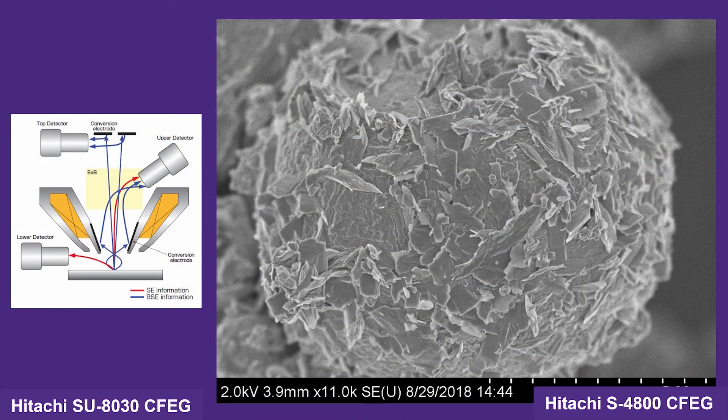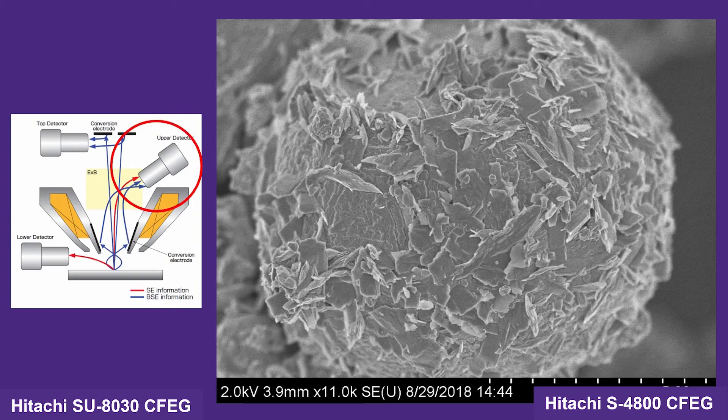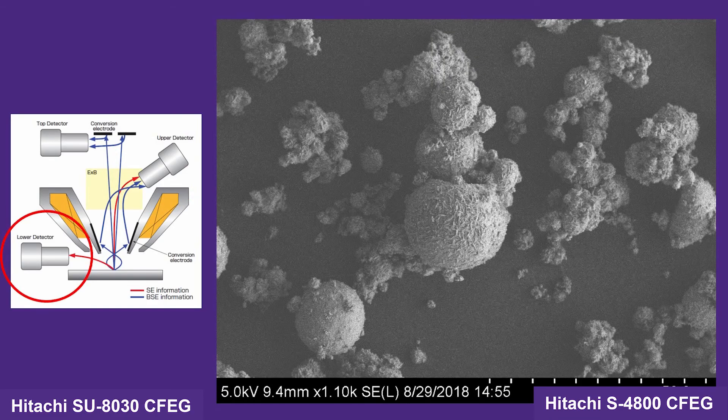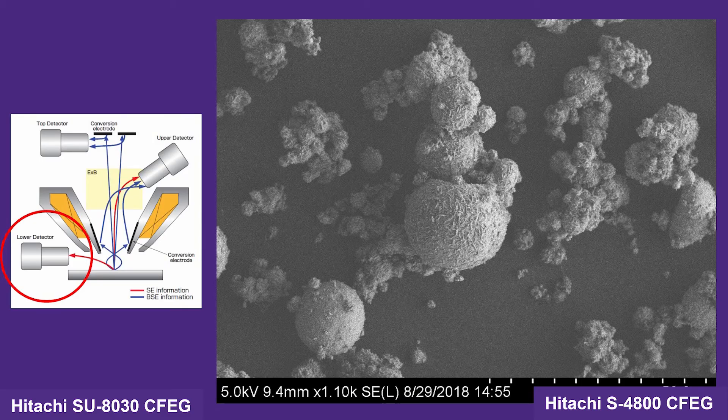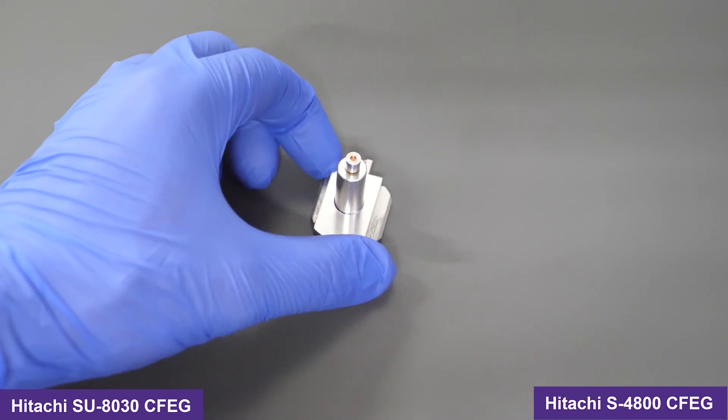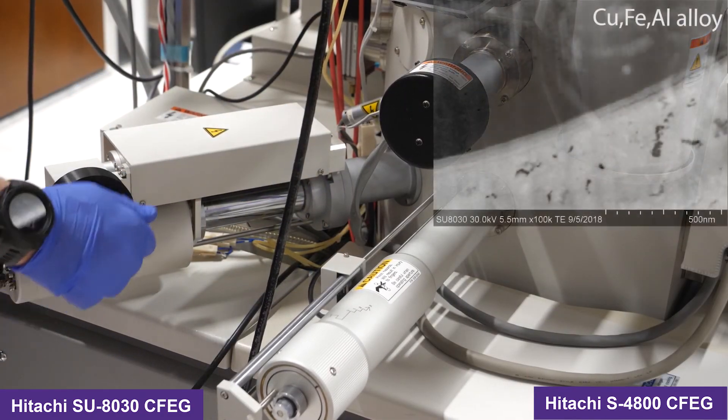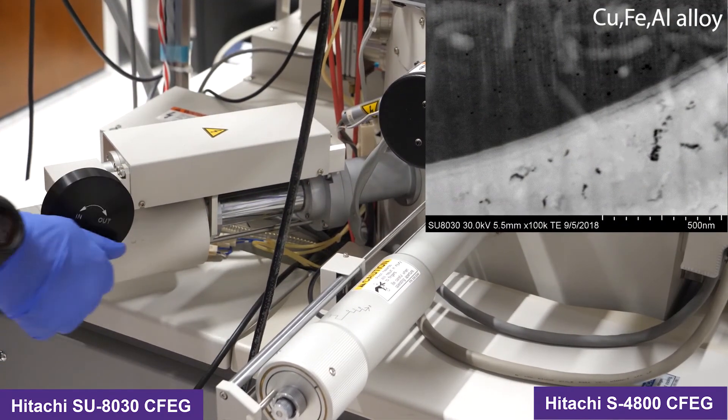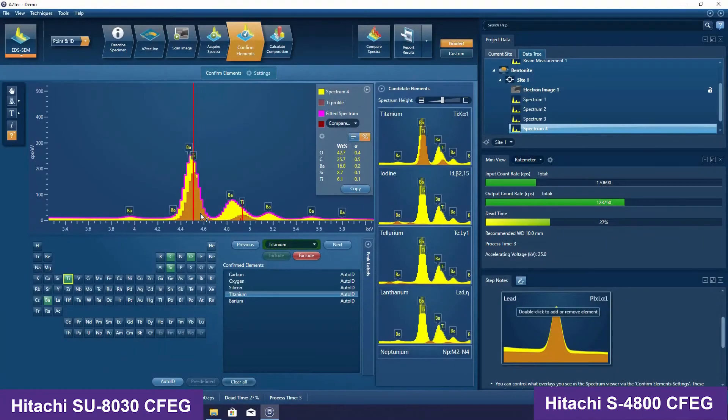Unlike the previous SEMs we saw, this SEM is equipped with an upper in-lens detector for ultra-high resolution imaging, as well as the traditional lower detector for topographical imaging. The SU8030 also has a dedicated STEM detector for low-kV bright-field STEM imaging and an EDS detector.